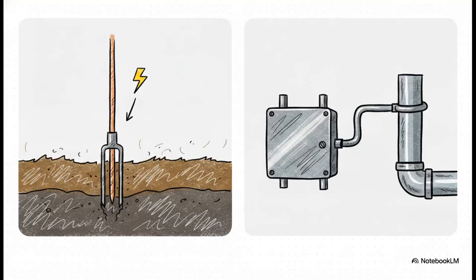Next, I want you to notice the difference between two concepts that get confused all the time: grounding versus bonding. They work together, but they do very different things. Grounding involves connecting electrical systems directly to the earth—literally a path straight down into the dirt below your house. This gives excess electricity a safe avenue to dissipate if there's a fault, like a lightning strike or a massive power surge.